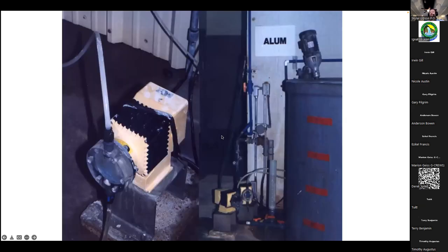There are two other check valves often forgotten: one at the chemical injection point and another in the foot valve — which is simply a check valve at the inlet. When cleaning the internal checks, also clean these. In total, this style of pump can have up to four check valves to maintain. Also be aware of containment — if a pump failure causes a leak, know where that chemical is going to prevent a spill within your facilities.